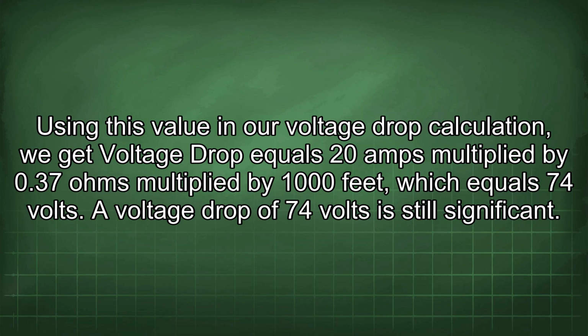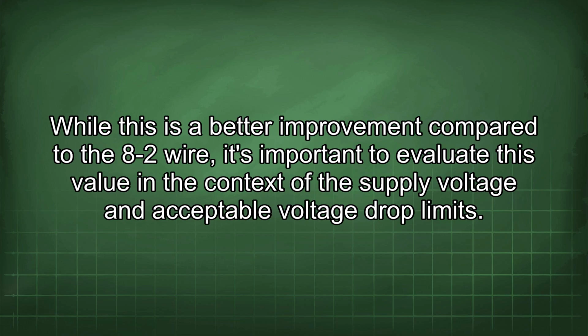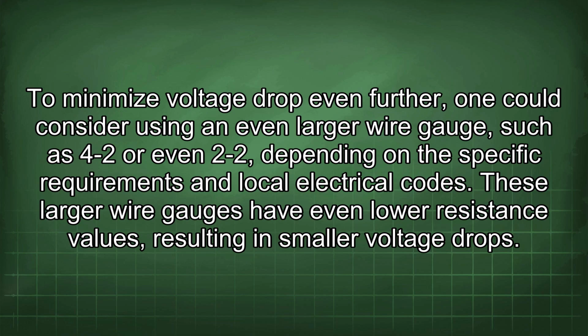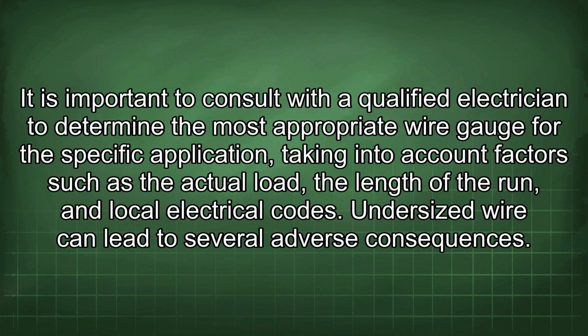A voltage drop of 74 volts is still significant. While this is a better improvement compared to the 8-2 wire, it's important to evaluate this value in the context of the supply voltage and acceptable voltage drop limits. To minimize voltage drop even further, one could consider using an even larger wire gauge, such as 4-2 or even 2-2, depending on the specific requirements and local electrical codes. These larger wire gauges have even lower resistance values, resulting in smaller voltage drops. It is important to consult with a qualified electrician to determine the most appropriate wire gauge for this specific application, taking into account factors such as the actual load, the length of the run, and local electrical codes.